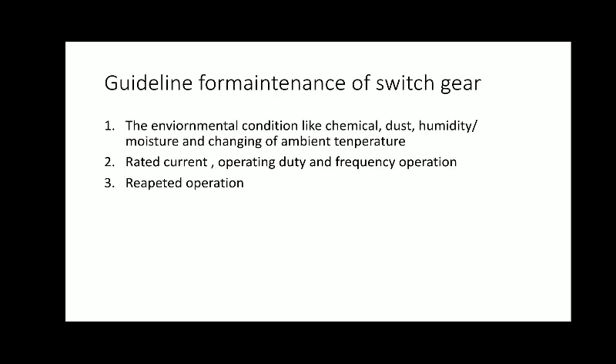A regular inspection and servicing is required for removing dust, damp and corrosion, etc. from the fixed part. Okay, next one, there is another part, which is a fixed part. One fixed part, one moving part. So from the fixed part, what type of inspection is done, what type of servicing is required? That is removing of the dust, damp, corrosion, etc. from the fixed part. This part is continuously fixed in one place. So because of that, regular inspection or regular removing of dust, dirt, or corrosion from this part is needed.